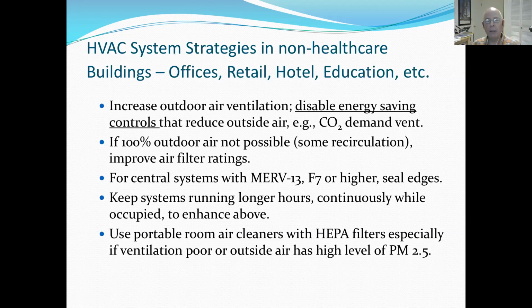In this climate, unless you have a system which is designed for 100% outdoor air, and sometimes industrial systems, like in a wood shop, are designed for 100% outdoor air. You can't recirculate the potentially explosive dust-laden air from a wood shop. So sometimes these systems can deliver outside air, but most cannot. So if you can't, then the trick is to make sure you have at least some dilution with outdoor air, and that the mixture of outdoor and return air is filtered.